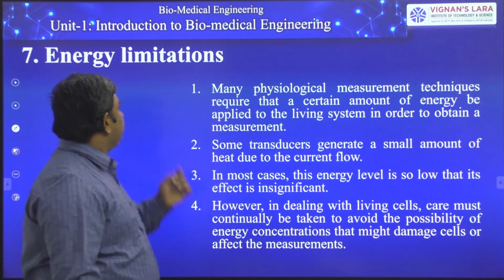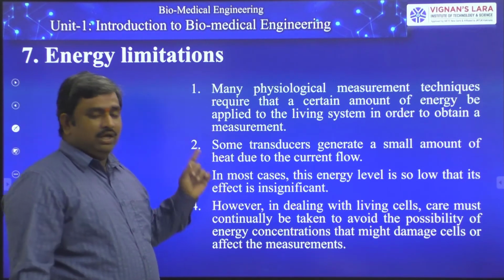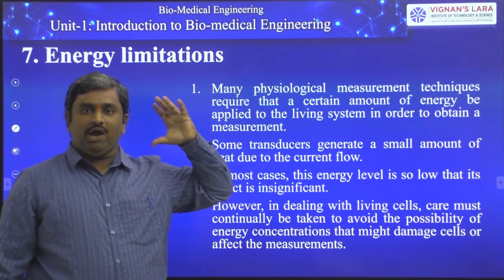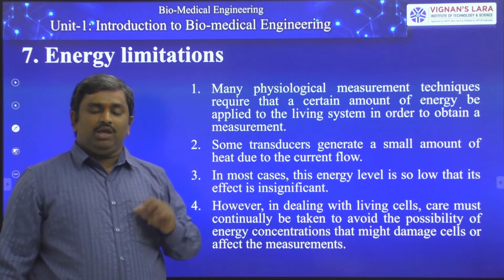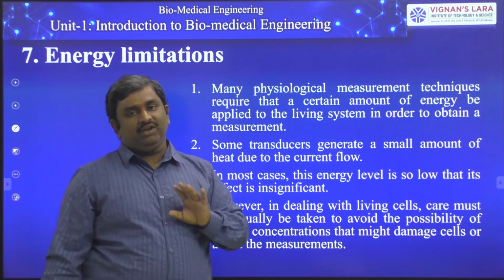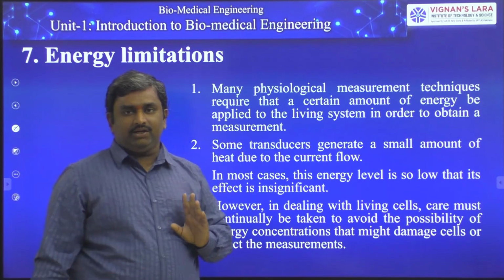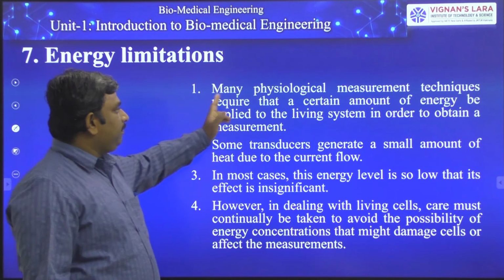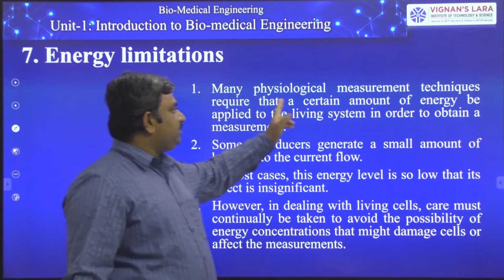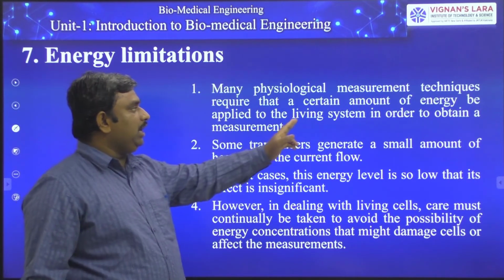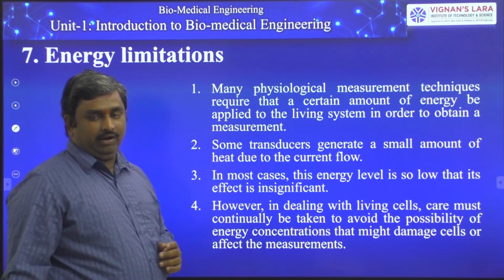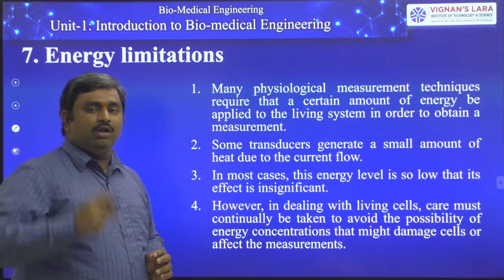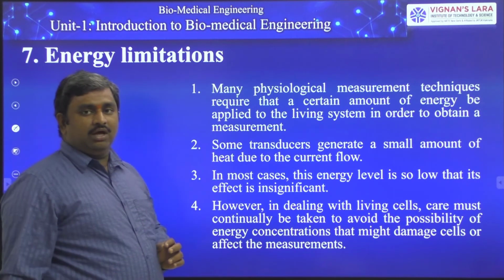Next, seventh one, energy limitations. Just now I said that regarding the effect of the transducer, you have to transfer sufficient energy from the transducer. A sufficient amount of energy is very helpful to identify the correct behaviors of the patient. If you send more than that, a lot of problems will occur. Many physiological measurement techniques require that a certain amount of energy be applied to the living system in order to obtain a measurement. For measuring different types of parameters from the human body, we need to send some limited voltage to the body. Otherwise, we cannot measure.